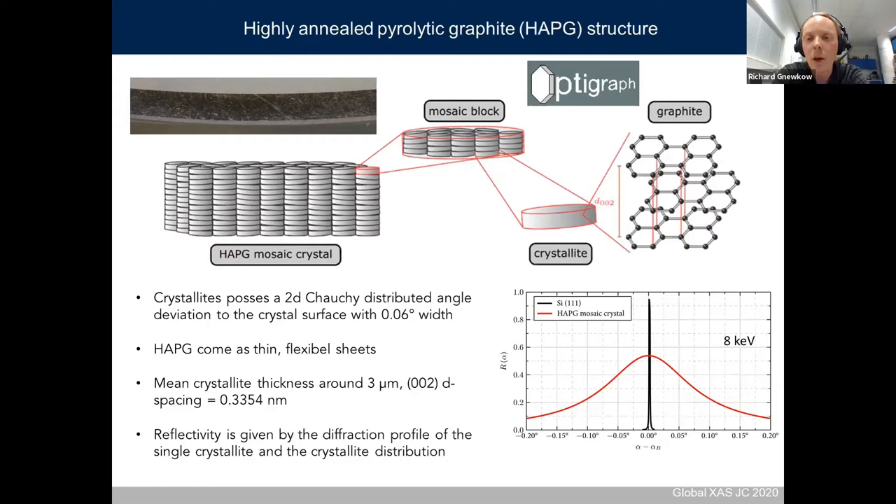How is this possible? It's a graphite crystal, but not a perfect crystal — there are small interlayer defects creating independently scattering domains called crystallites, which are assumed to be perfect crystals and make up the mosaic crystal. These small crystallites all have a small angle deviation to the crystal surface, described by a 2D Cauchy distribution with a typical width of 0.06 degrees. Due to this small angle deviation, the angle range where the crystal can reflect a single wavelength is correspondingly increased.